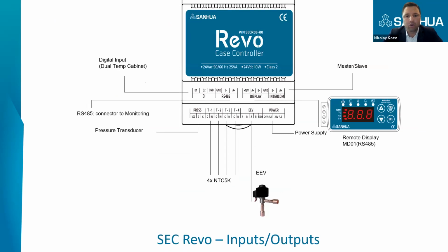So let's look at the inputs and outputs. On the bottom, we have the connections for the electronic expansion valve, temperature sensors and the pressure transducer. Also, we have the power supply, the communication port, and the remote display, which can be used to monitor the temperature of the cabinet or cold room, but also to make all the settings of the controller. These controllers can be connected in master-slave operation. We also have a digital input for dual temperature cabinets. So we have 2 set points, one for example medium temperature and one low temperature, and the technician can switch between the 2 set points depending on needs.